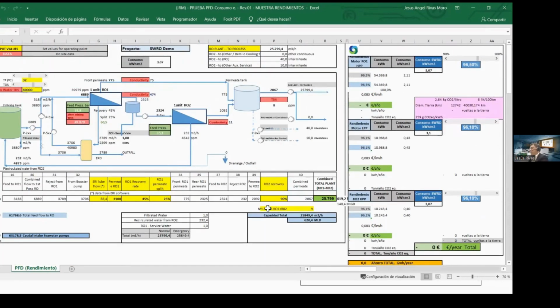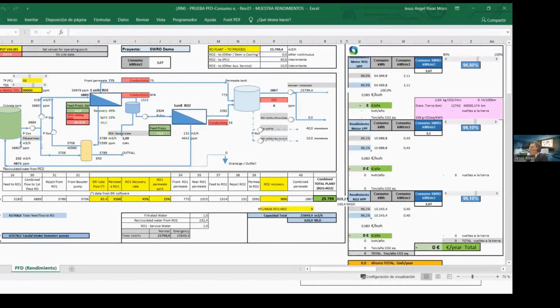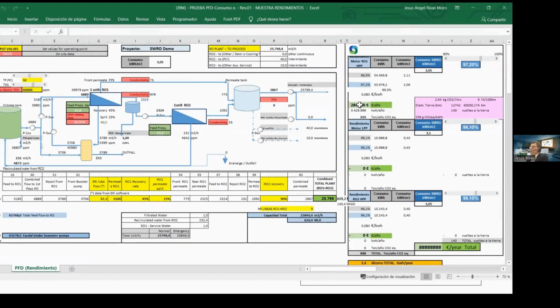Okay, with these values, we play here with the consumption, and I repeat, just modifying the consumption. With all I told you before, the wire, the losses, the bearings, the fan, the cooling methods, the power supplies, and so on, we can consider just increasing the efficiency of the motors. And let's see the impact in this Excel file. If we modify, you see here, there are no savings, considering one price for the kilowatts. If we increase this efficiency just for the high pressure pump from 96.5, which is in the specs, to, let's say, 97.2, which we can achieve, you can see a very big increase in efficiency, which goes to a lot of savings, considering the cost of the energy, of almost $300,000 or euro per year.